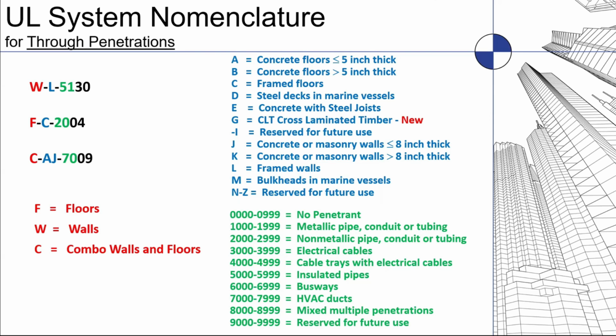The green lettering tells you what the metallic or penetrant material is. So looking at the top one - W wall, L framed, 51 - that's in the 5000 series, which is an insulated pipe. So it's an insulated pipe going through a framed wall, and the black number 30 is just a sequential number, meaning it's the 30th test done in that type of combination. That's how you walk through these listings.